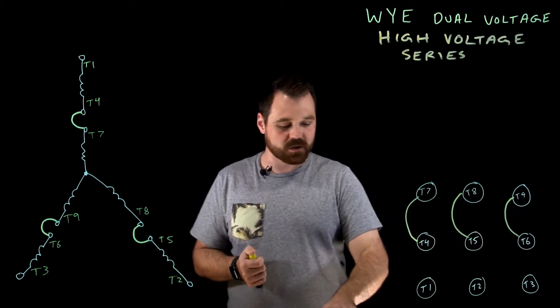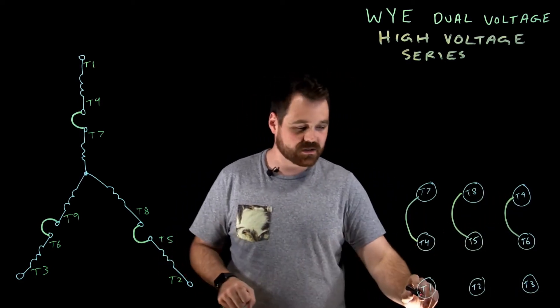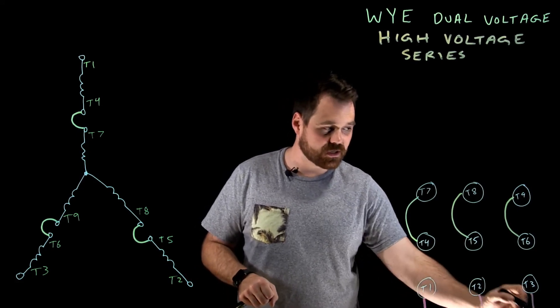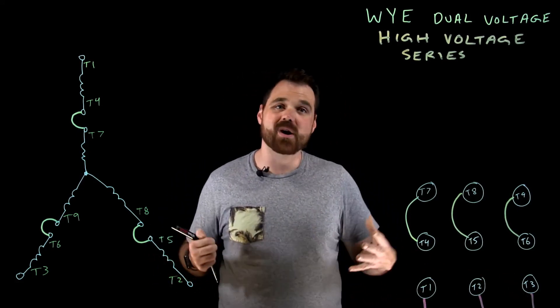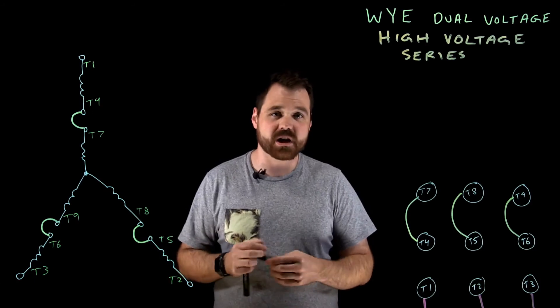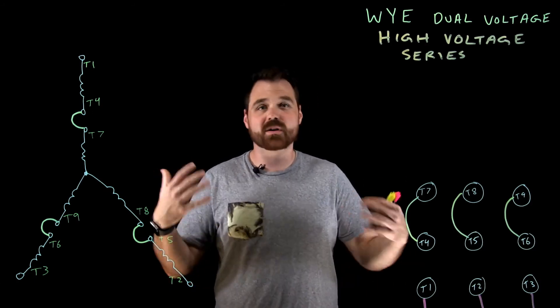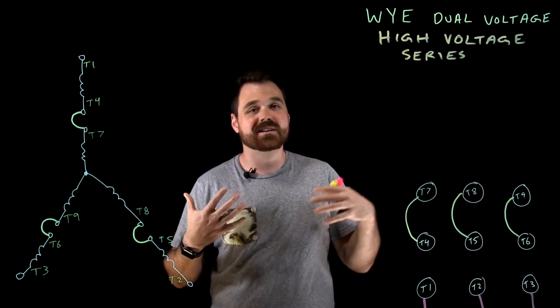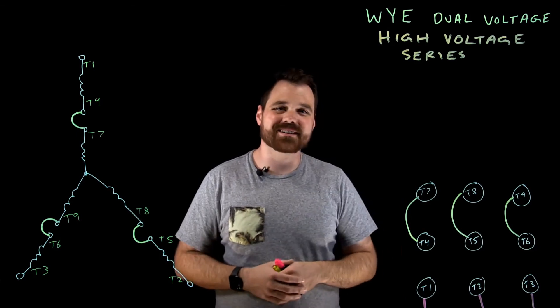And then of course, we definitely don't want to forget, we need to connect T1, T2 and T3 down to my line one, line two and line three conductors. Now that would make this motor run in a high voltage situation because our windings are connected in series.